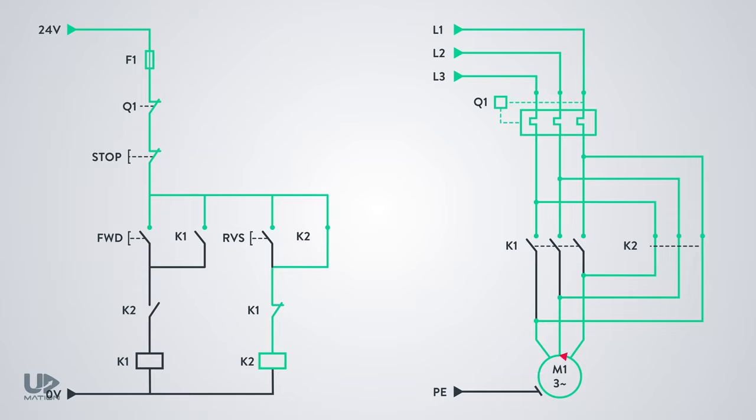circuit. This is an NC contact from the power circuit breaker, which cuts the power from the control circuit in case of overload or short circuit. Therefore, to keep the motor safe, the run commands will be removed from the motor immediately. By pushing the stop push button, as it also has a normally closed contact, we can turn off the process manually.